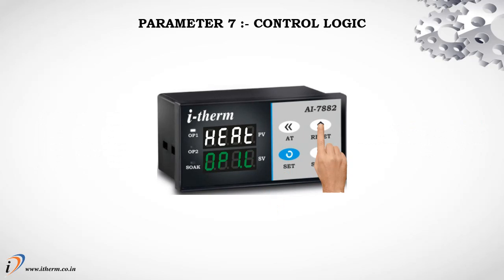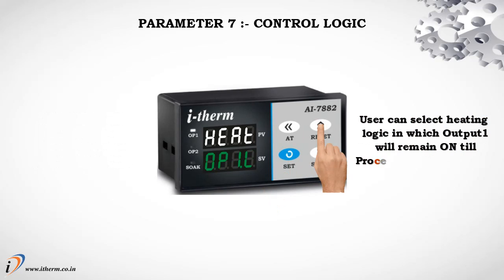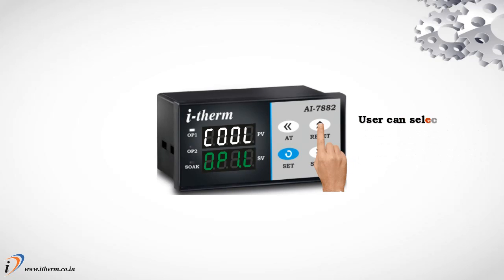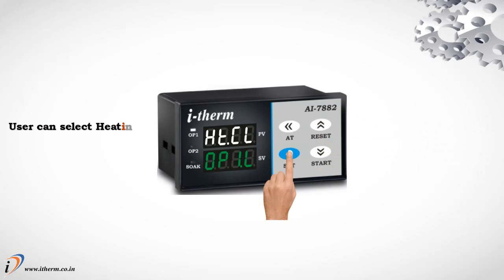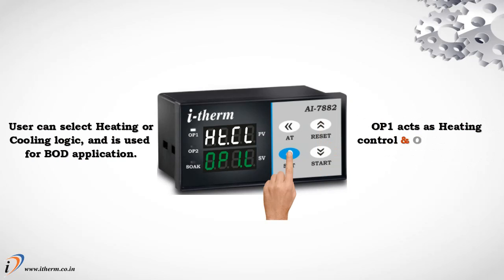Parameter 7, Control logic. The user can select heating logic, in which output 1 will remain on until the process value is less than the set point. The user can select cooling logic, in which output 1 will remain on till the process value is more than the set point. The user can select heating or cooling logic, used for BOD application. Output 1 acts as heating control and output 2 as cooling control.